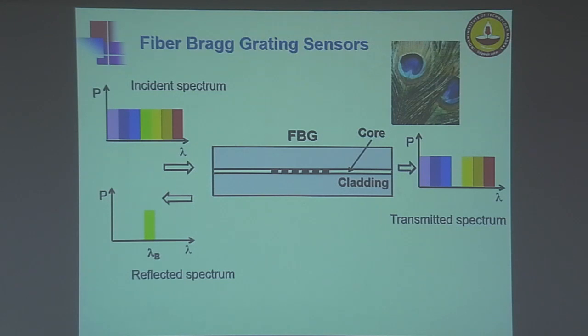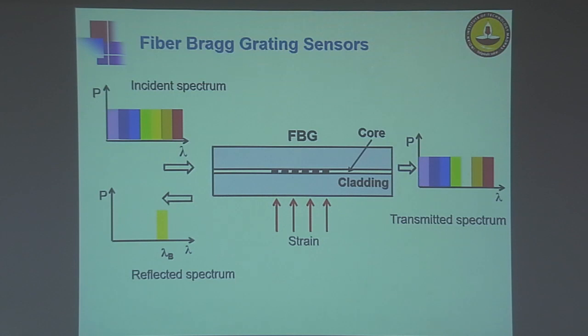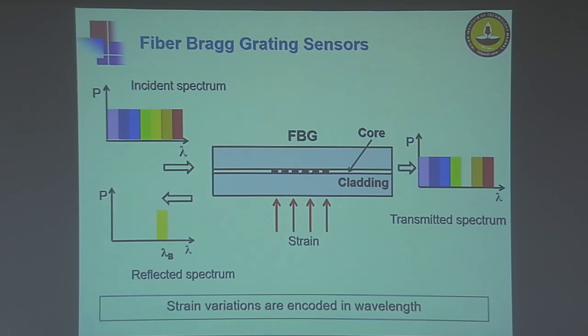The grating obeys Bragg's diffraction theory, and it has been shown that the peak wavelength of reflection — known as the Bragg wavelength — is a function of the effective refractive index and the period of the grating. But how do we use this element as a sensor? If the grating is subjected to a strain, it changes the grating period and the effective refractive index, thereby changing the Bragg wavelength — so now the grating is reflecting a different color. In some sense, the strain variations are encoded in the wavelength of the reflected light. This is attractive because information encoded in wavelength is generally impervious to noise and can be transmitted over long distances without being corrupted by noise.